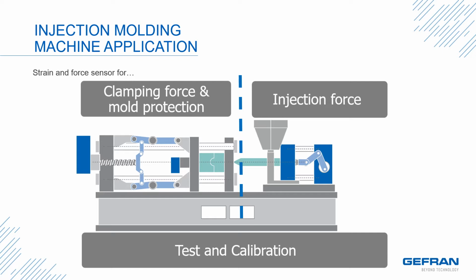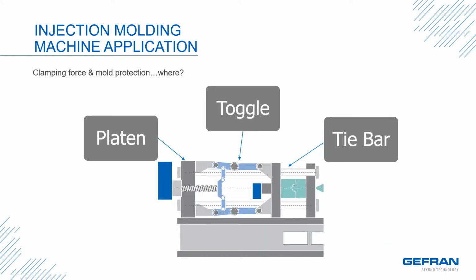Here is an injection molding machine application where you can use strain and force sensors for test and calibration for specifically injection force in the machine itself and for clamping force and mold protection. Again, in this application, where specifically do we take a look at the clamping force and mold protection? As you can see from the picture, it is in the tie bar area itself, the toggle area of the machine, and the platen, the force of the tie bars putting force on the platen itself.